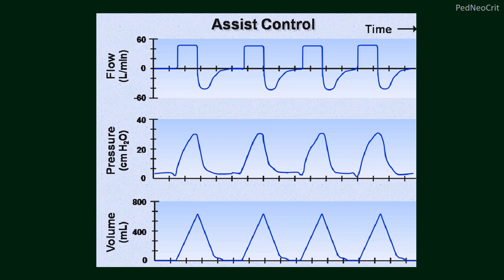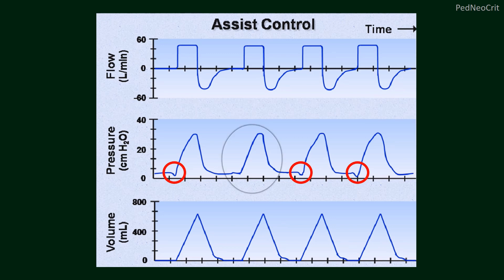All breaths, once triggered — either patient-triggered or time-triggered — are treated the same and have a constant tidal volume or peak inspiratory pressure. This is the waveform in assist control ventilation: the top is flow waveform, middle is pressure waveform, and bottom is volume waveform. All breaths are of similar character and provide equal tidal volume. In the pressure waveform, you will notice negative indentations before some breaths — these indicate the patient's spontaneous effort, meaning those are patient-triggered breaths. Where there is no negative indentation, that is a machine-triggered or time-triggered breath.